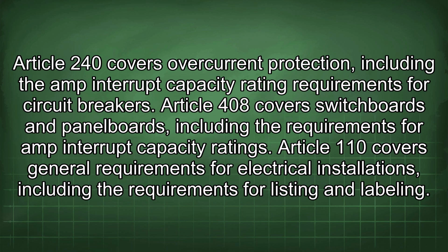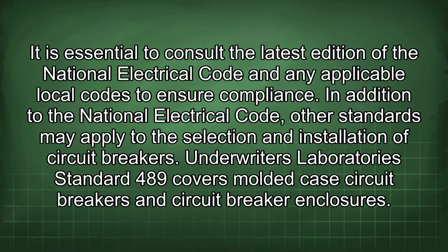Article 408 covers switchboards and panel boards, including the requirements for amp interrupt capacity ratings. Article 110 covers general requirements for electrical installations, including the requirements for listing and labeling. It is essential to consult the latest edition of the National Electrical Code and any applicable local codes to ensure compliance. In addition to the National Electrical Code, other standards may apply to the selection and installation of circuit breakers.